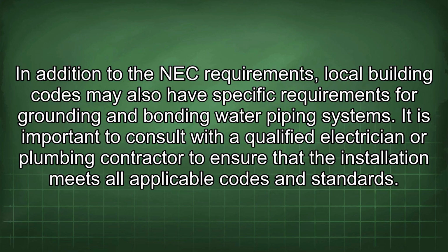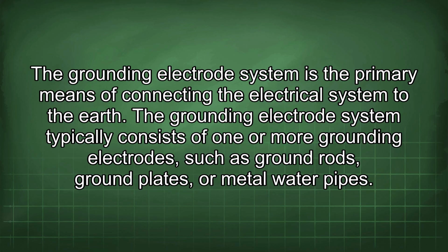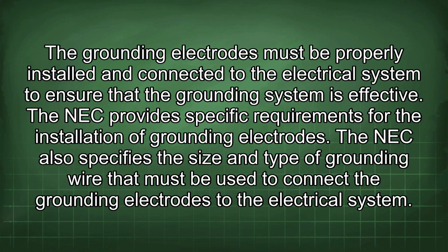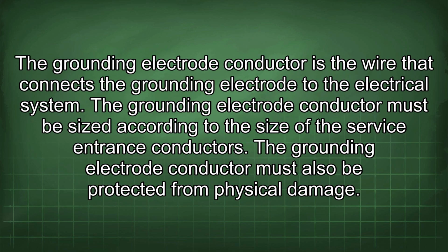The grounding electrode system is the primary means of connecting the electrical system to the earth. The grounding electrode system typically consists of one or more grounding electrodes, such as ground rods, ground plates, or metal water pipes. The grounding electrodes must be properly installed and connected to the electrical system to ensure that the grounding system is effective. The NEC provides specific requirements for the installation of grounding electrodes. The NEC also specifies the size and type of grounding wire that must be used to connect the grounding electrodes to the electrical system. The grounding electrode conductor is the wire that connects the grounding electrode to the electrical system. It must be sized according to the size of the service entrance conductors and must also be protected from physical damage.